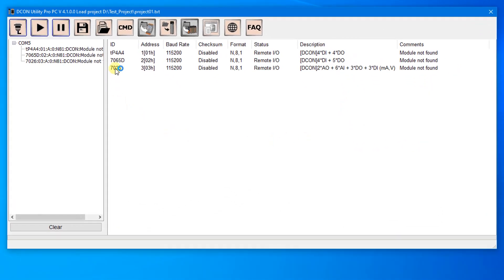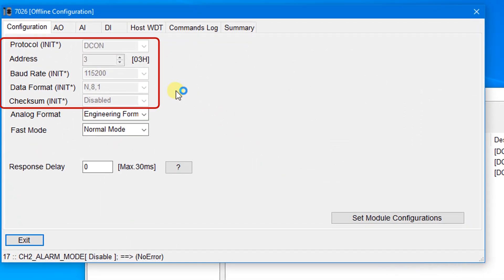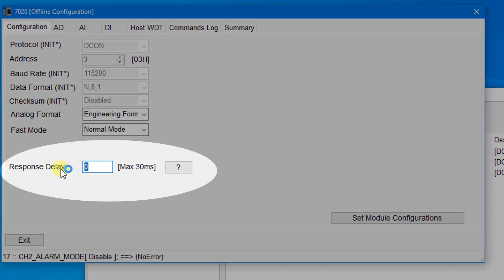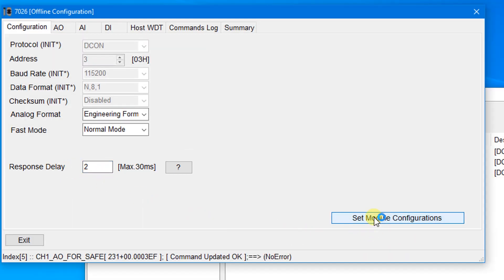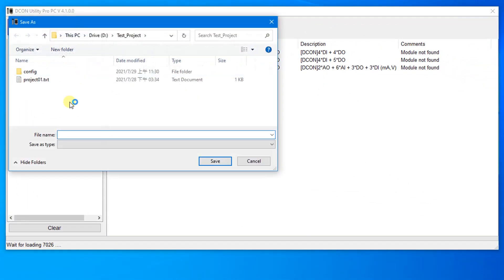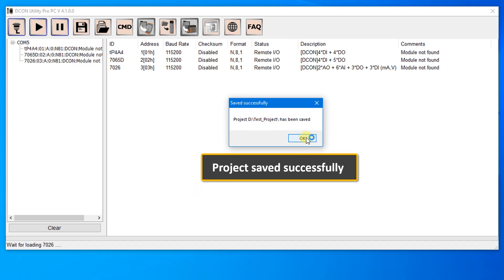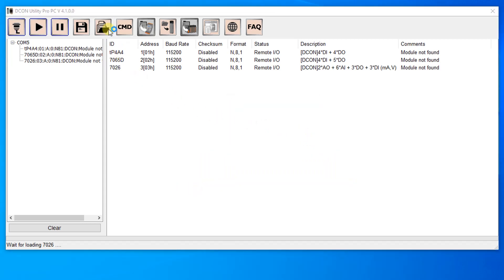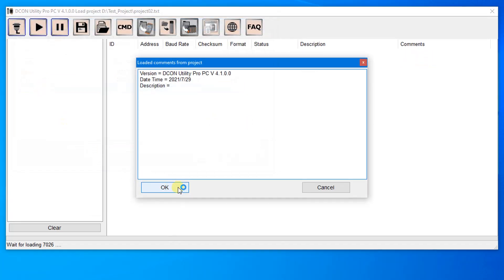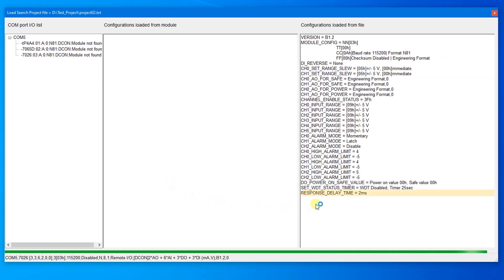Users can change configurations without connecting the module. You can change IO settings in the offline configuration window, except for communication parameters. In this example, set the response delay to 2 ms. Click the button to save the value and close the window. Then click the Save Project button to save the changes — you can save the file as Project 02.